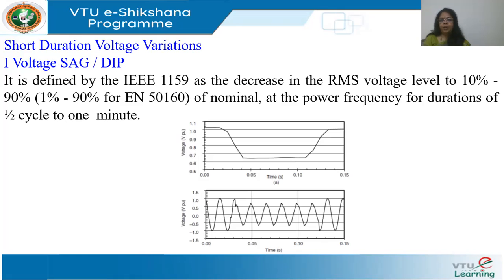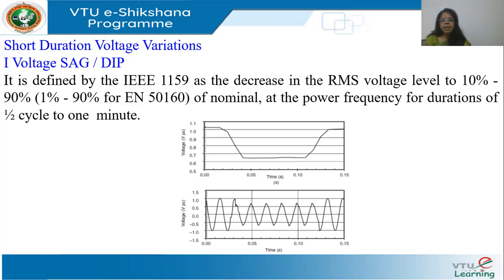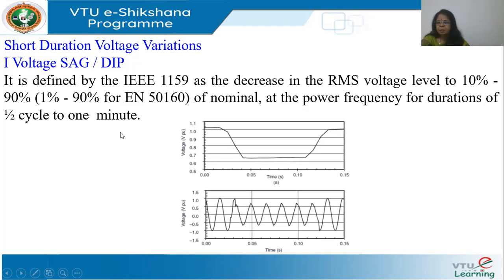Short duration voltage variations begin with voltage sag — IEEE uses 'sag' while IEC uses 'dip,' but both mean the same thing. The IEEE 1159 standard describes a sag as a decrease in RMS voltage to between 10 to 90 percent (0.1 to 0.9 per unit). The European standard EN 50160 describes it as 1% to 90%.